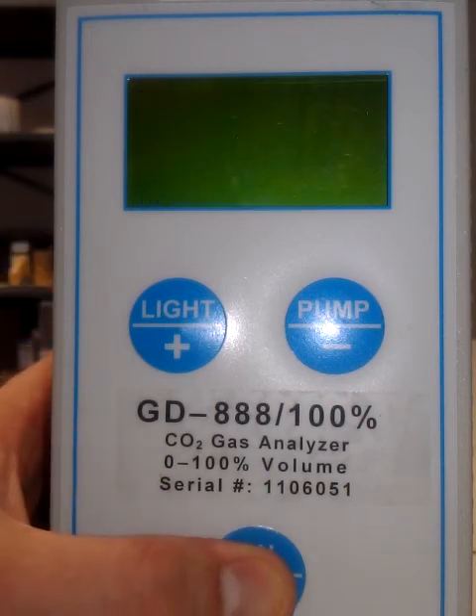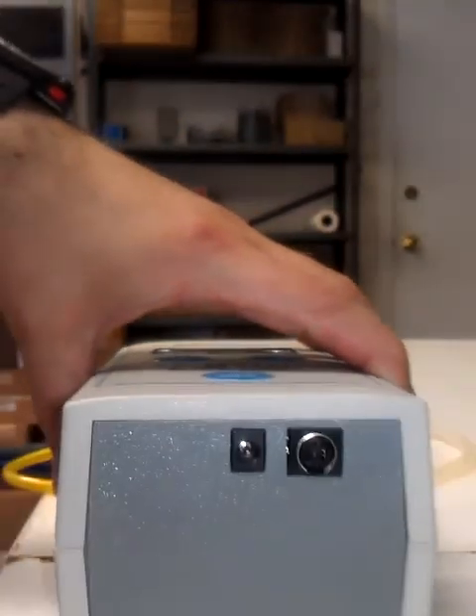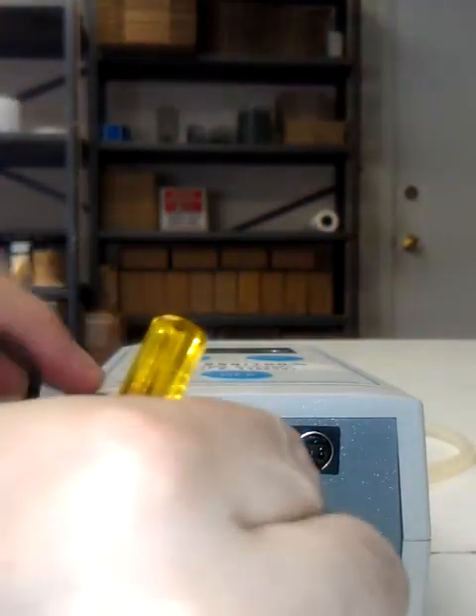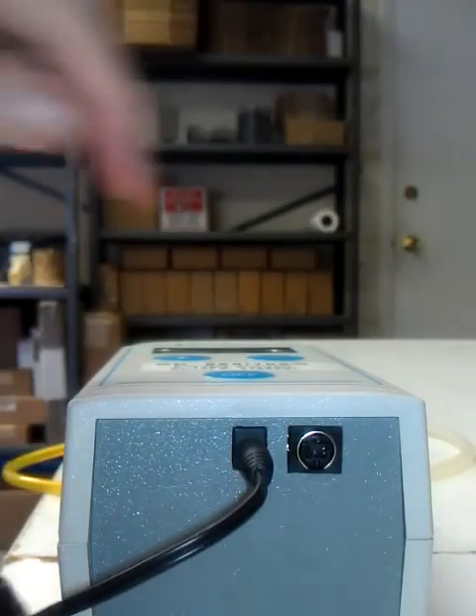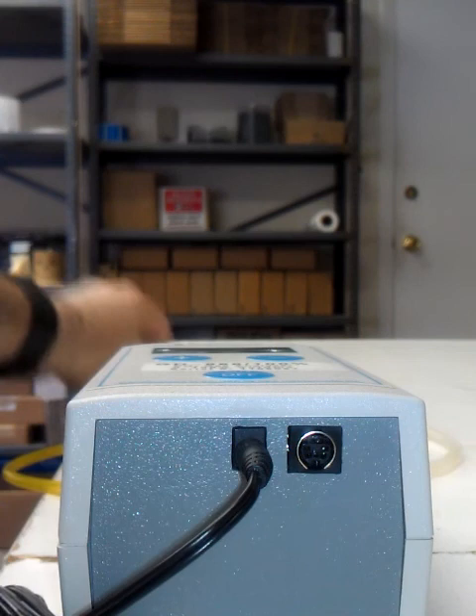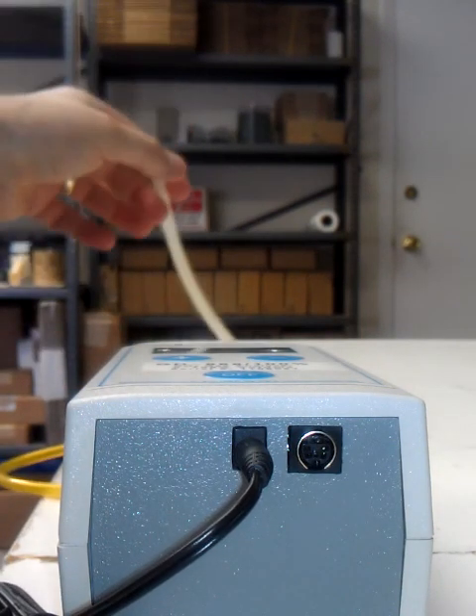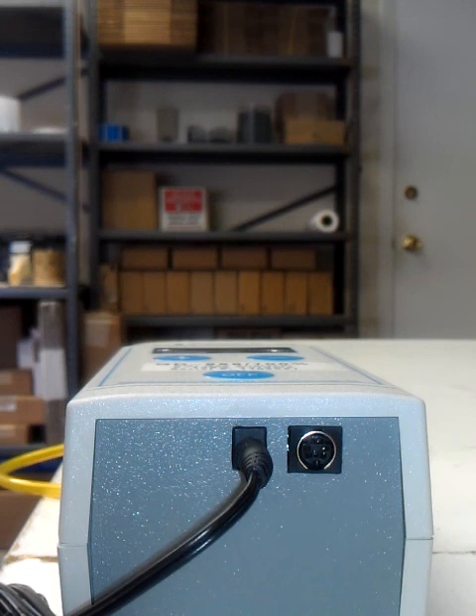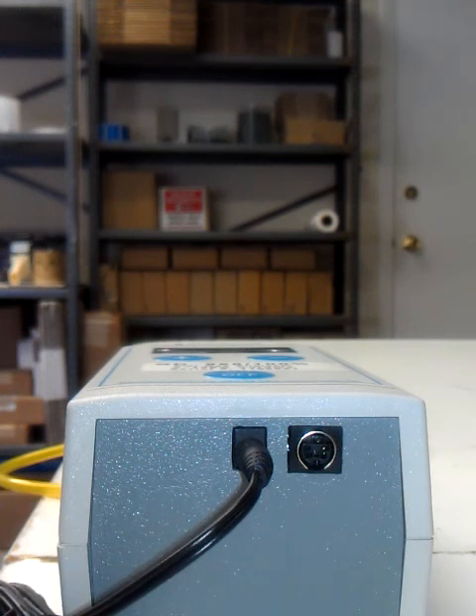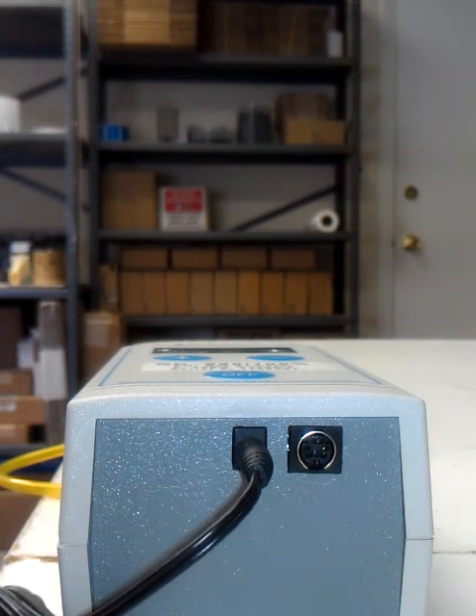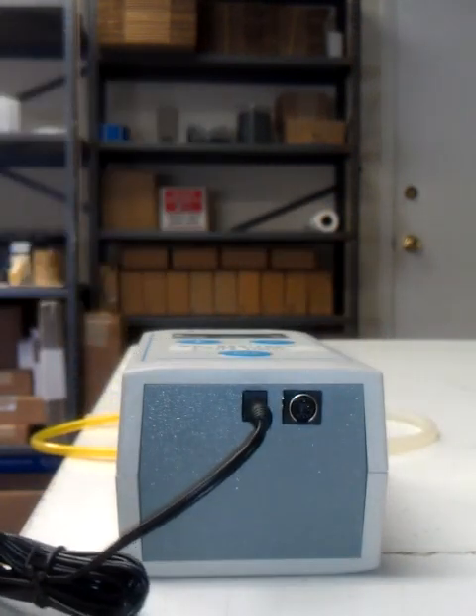You can turn it off, put it back down in the case, reconnect the power, and your data logger, and then turn it on and get your sampling. It is usually more precise if the units have been on for a few minutes before you start taking your readings, so they all can equilibrate and get proper readings, but they should all be the same if turned on the same time, if all calibrated the same procedure. They should all be extremely close of each other. That concludes the calibration portion of the GD units.